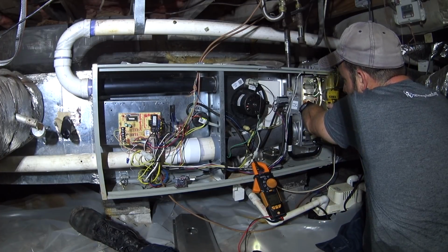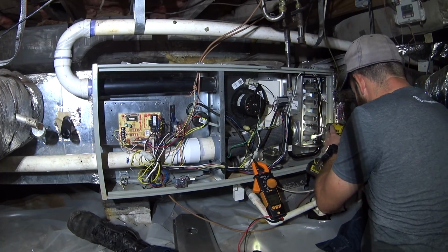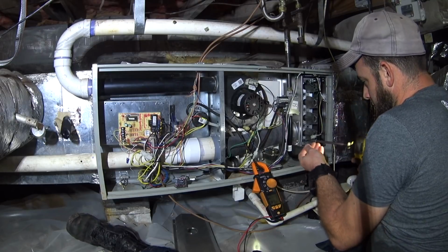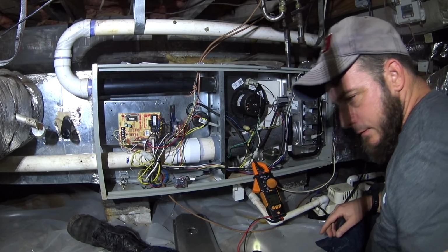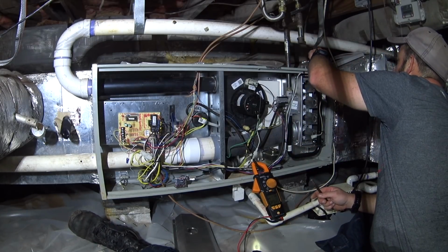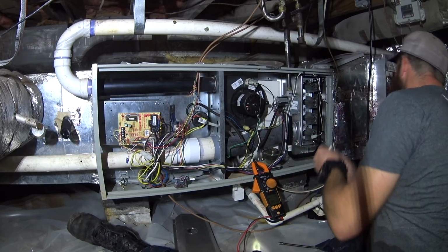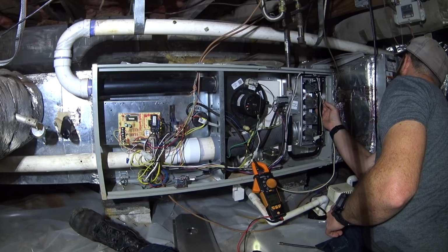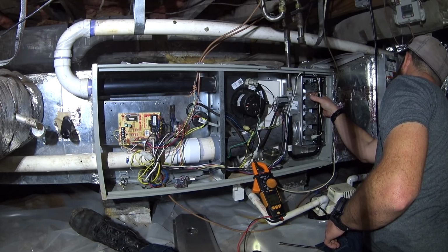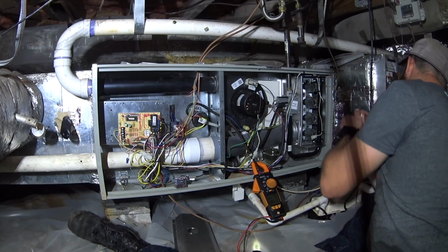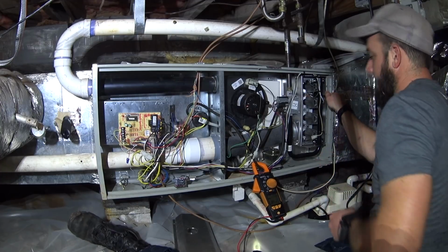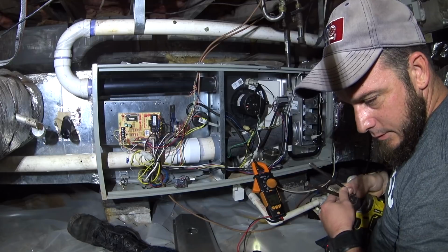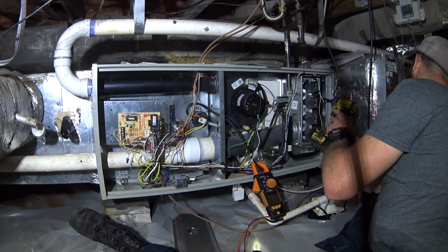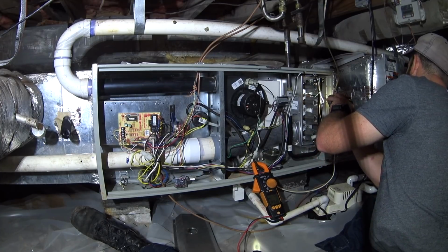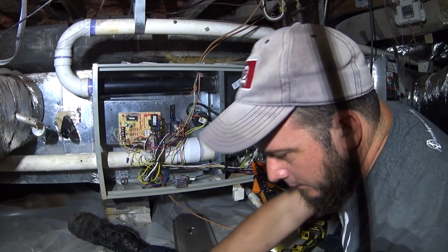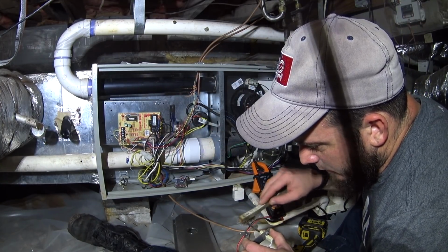Looks like we got lucky this time. A lot of times the burners will try to fall out as you're putting them in when they're assembled in a vertical manner like this. All right, flame sensor back in there. That can also be sometimes difficult because the flame sensor is not easily accessible to hold it still while you're trying to get it back into the position where the screw will hold it down.